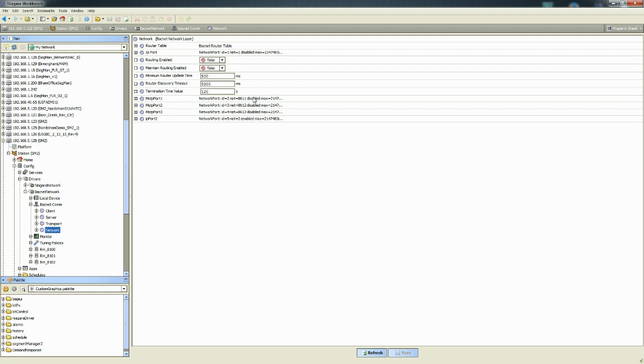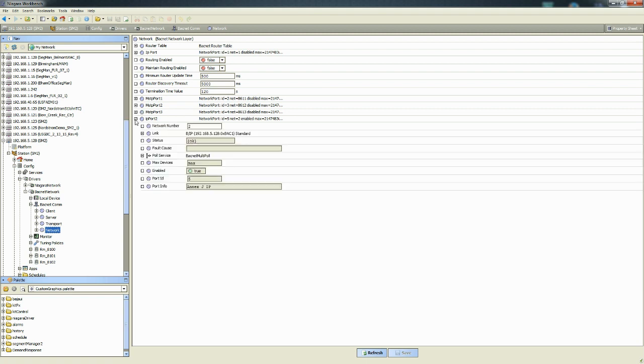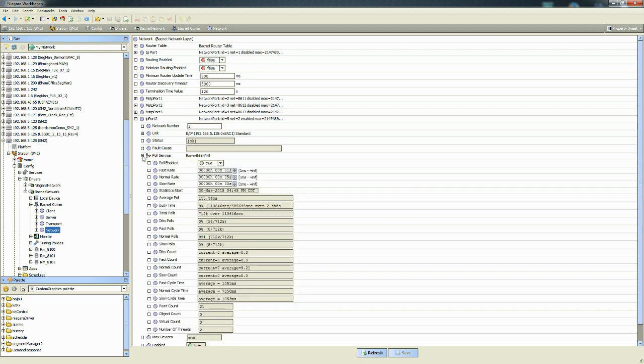If you were using a LMSM-6E, you may be using MSTP ports 1, 2, and 3. So the changes we make on IP port 2 would need to be repeated for the 3 MSTP ports. In an IP router situation, we only need to do it on this one port. So let's take a look at that. I'm going to expand IP port 2 and then find poll service and expand it.